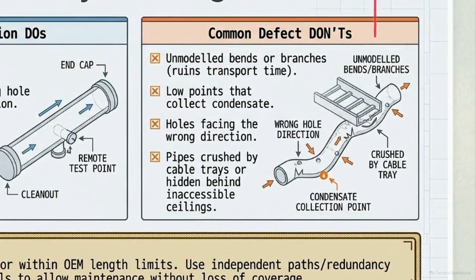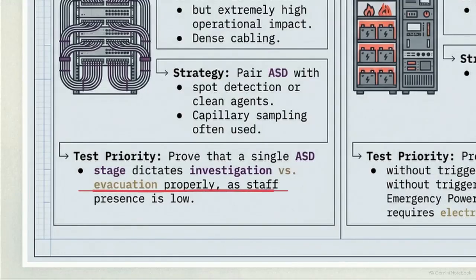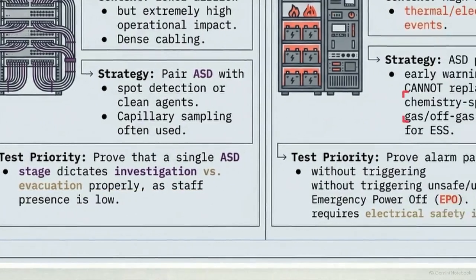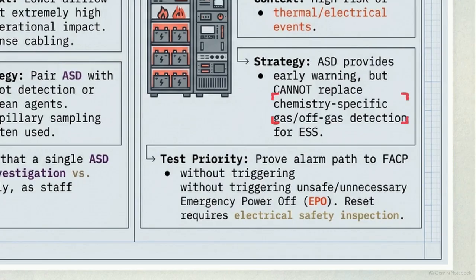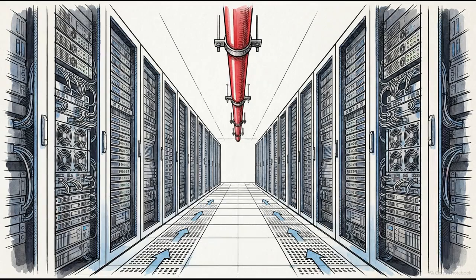Common errors include unmodeled pipe branches or sampling holes facing the wrong direction. Additionally, pipes can be crushed by overlapping cable trays or develop low points that collect airflow blocking condensate. In ICT rooms, the test must prove the system accurately distinguishes between investigation and evacuation. In battery rooms, ASD cannot replace chemistry-specific detection. Here, testing proves the panel alarm path without triggering an unsafe emergency power-off sequence. Successful implementation requires navigating physical constructability issues and environmental constraints unique to each room's specific electrical risk.